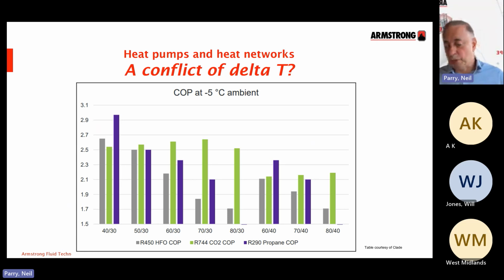That's not to say you should just ignore that and connect it straight up to existing buildings without any issue. Obviously, as I've explained, every effort should be made to optimize that building, to maximize the delta T within that existing building, move from 3-port to 2-port control, look at the heat emitters and so on, to optimize that delta T, and then couple it to something like a CO2 heat pump.